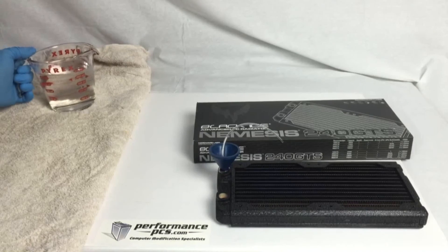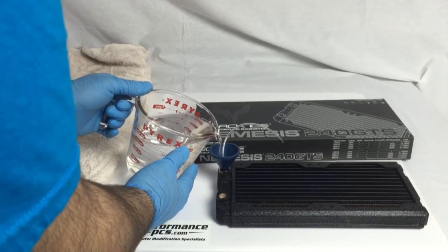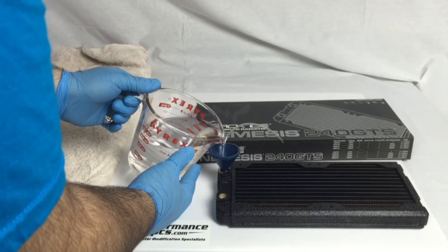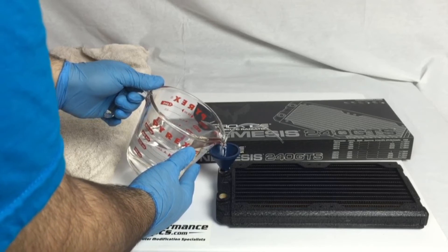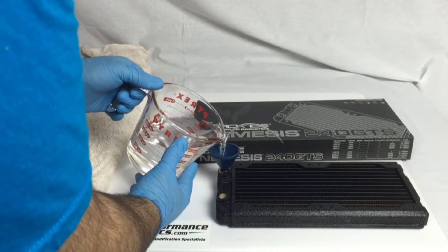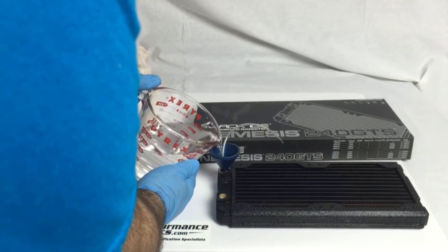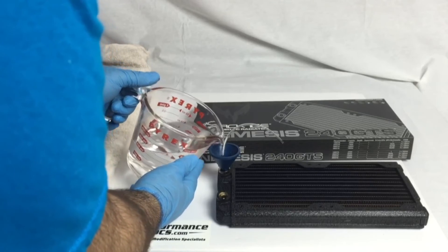Let's go ahead and get started. We're going to have this filling up slowly. You want to watch the other hole — on this Black Ice there's only one input and one output, so you don't have to worry too much. Just make sure all the other holes are capped. Keep your eye on it because eventually you'll start seeing it flow through the other side — you don't want to see it bubble out. We're going to stop right there and clean this up.